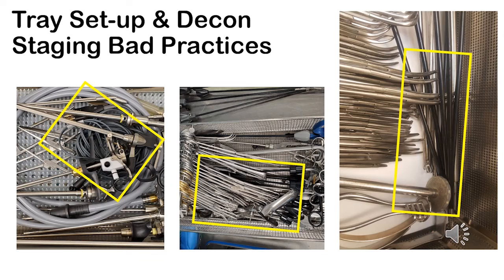So if you look at tray setup and the decontam staging, these are definitely bad practices. The picture on the left is a reusable bipolar cable that's mixed in with metal instruments, where you can see, where it's highlighted, that the scissors can definitely scrape and cut it. Beyond that, you can also see a light cable in there that's probably getting damaged as well.